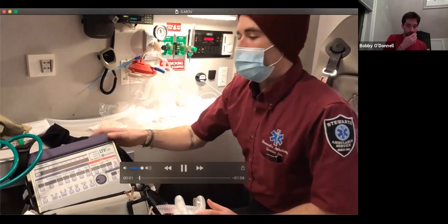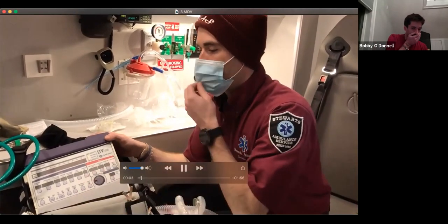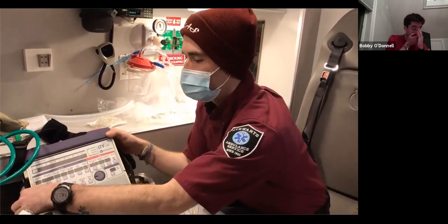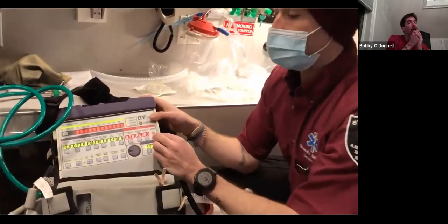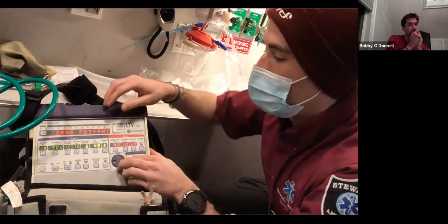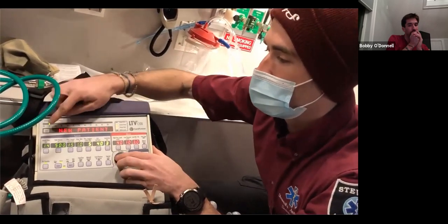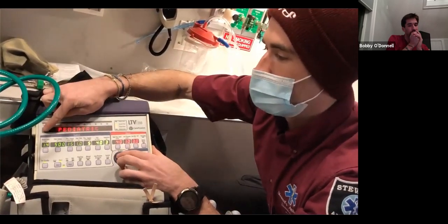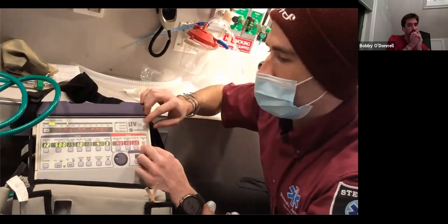All right. So we'll do CPAP first, because it's a few steps and it's easier sometimes to see how it works on the ventilator as opposed to just those written out steps. So same thing as if you're setting up the vent, you're going to change it to new patient, adult. So now we're in here.